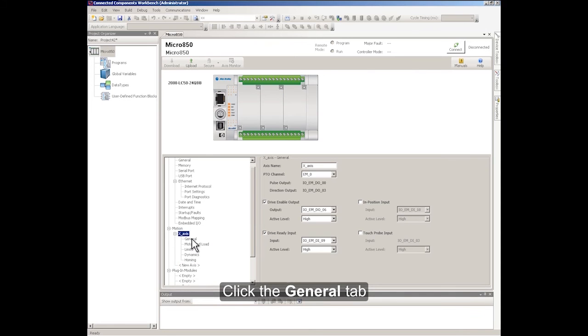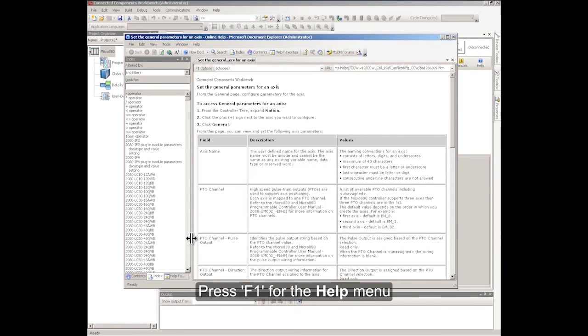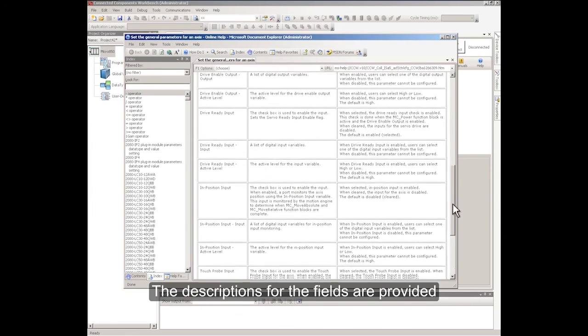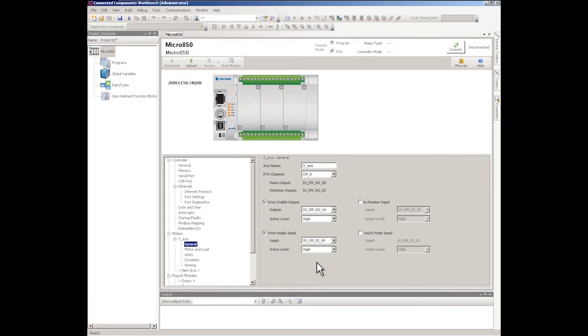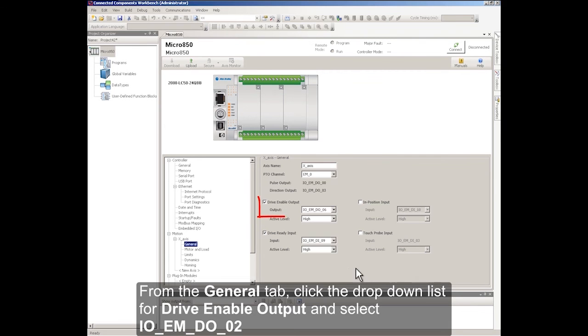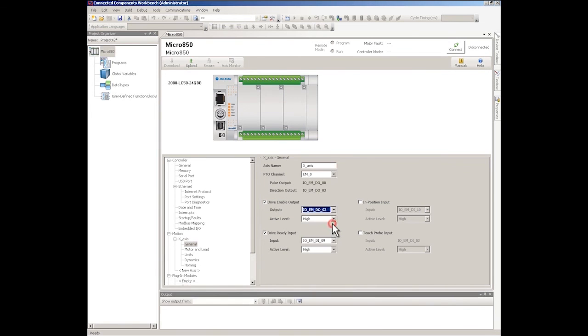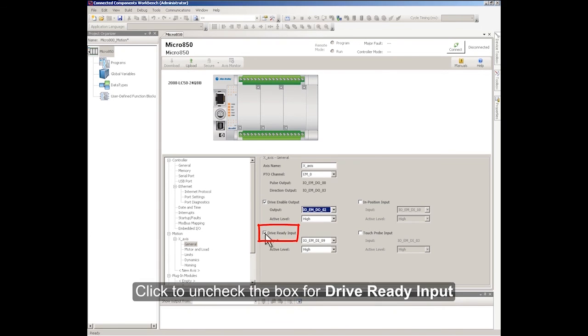Click the General tab. You can access the Help menu for more information about the field settings — press F1 for the Help menu. The descriptions for the fields are provided. Assuming you want to use Output 2 to enable your servo driver, from the General tab, click the drop-down list for Drive Enable Output and select Embedded Digital Output 02. Assuming you do not need the Drive Ready input, click to uncheck the box for Drive Ready input.